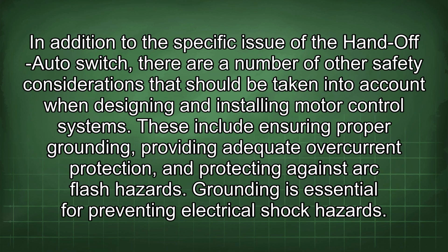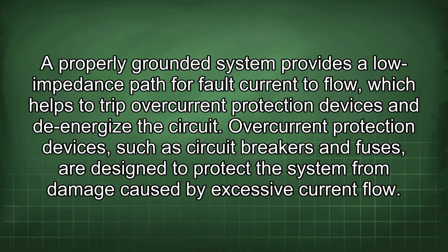In addition to the specific issue of the hand-off-auto switch, there are a number of other safety considerations that should be taken into account when designing and installing motor control systems. These include ensuring proper grounding, providing adequate overcurrent protection, and protecting against arc flash hazards. Grounding is essential for preventing electrical shock hazards. A properly grounded system provides a low impedance path for fault current to flow, which helps to trip overcurrent protection devices and to de-energize the circuit.